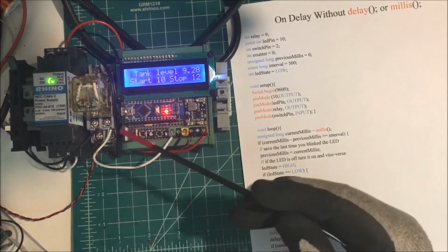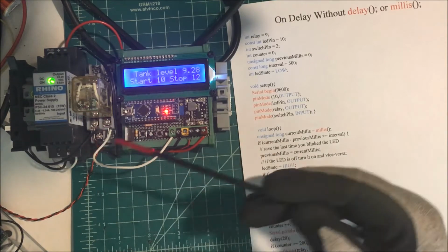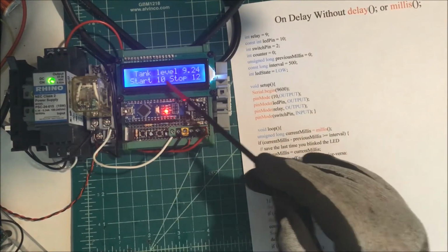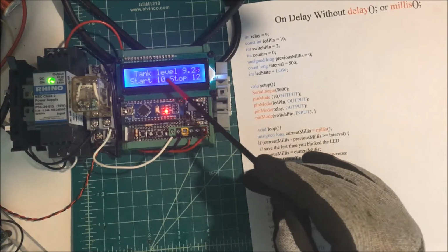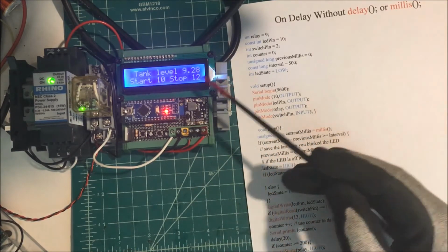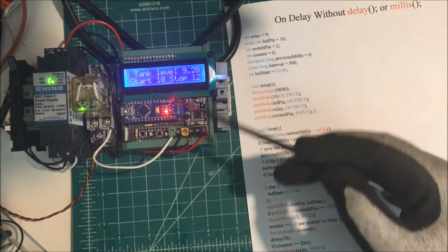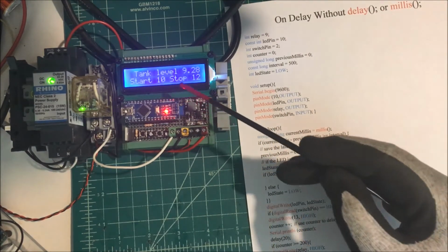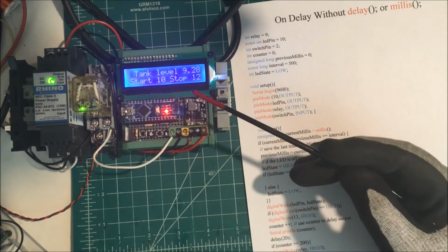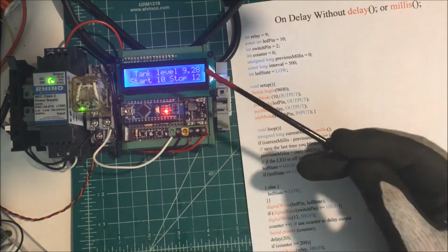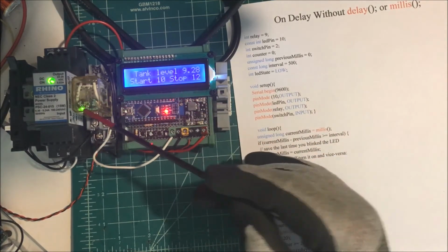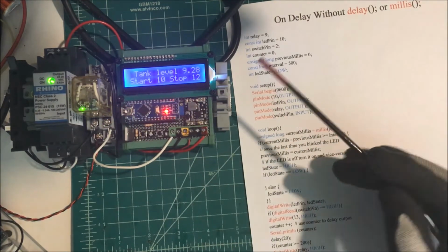I realize that there's check valves and foot valves in there that prevent that from happening, but those don't always work. And there's hysteresis built into this controller here from 10 to 12 feet in the tank. But I'm using a radio control from the tank down to this unit down here at the well. So something could go wrong there, and I could be stopping the well pump. So I just have a little delay in the relay here for a little added safety.